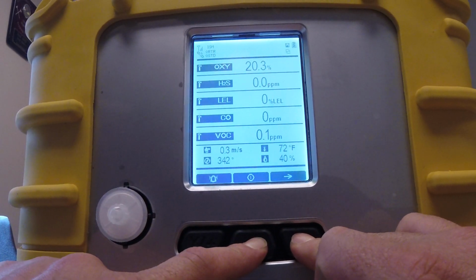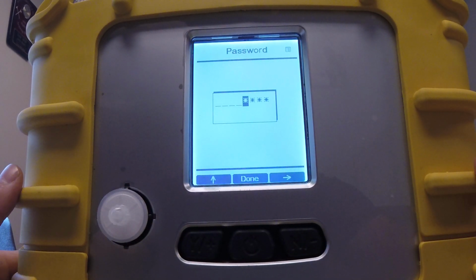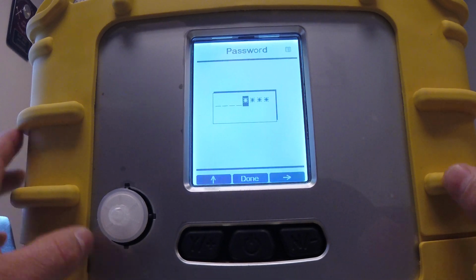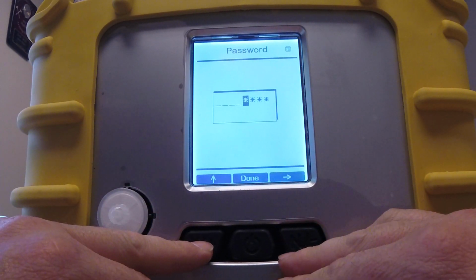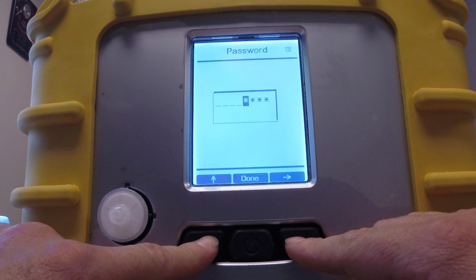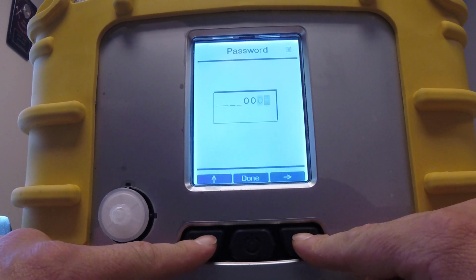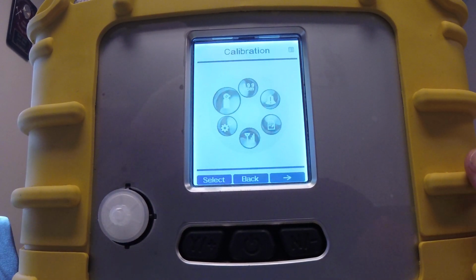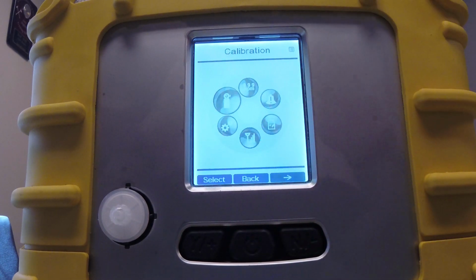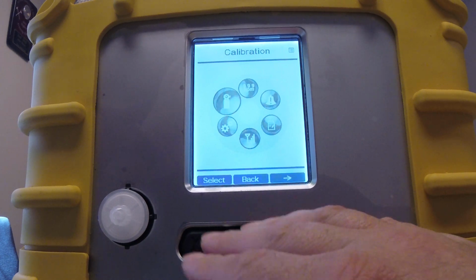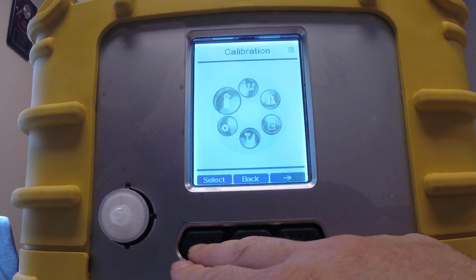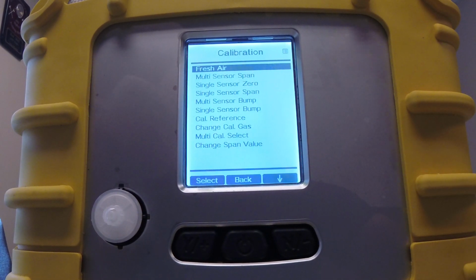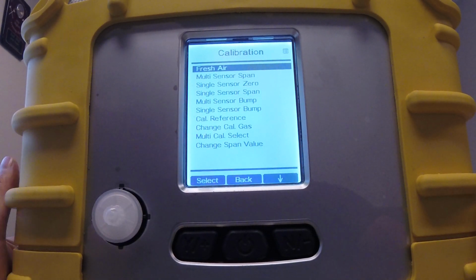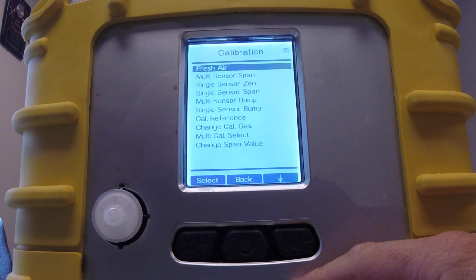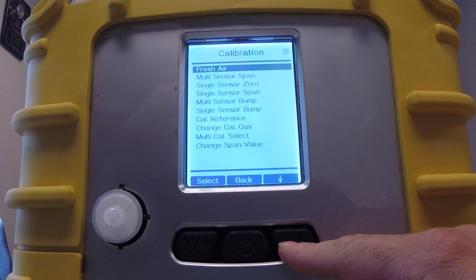So we're going to hold the power button and the no button or minus button together. This is going to get us into our main menu. The password for all of our new equipment, we're just going to keep it the same. Everybody's going to know the password. It's going to be 0000, at least for now. Done. That'll give us our main screen. So really for the purposes of this training, we're only going to hit on entering the menu to get to the calibration. Reason being is this is where we have our calibration for calibrating the instrument if we need to out in the field, as well as when we do a bump test, as we should with all of our gas instruments before and after the call when we're deploying and wrapping up.